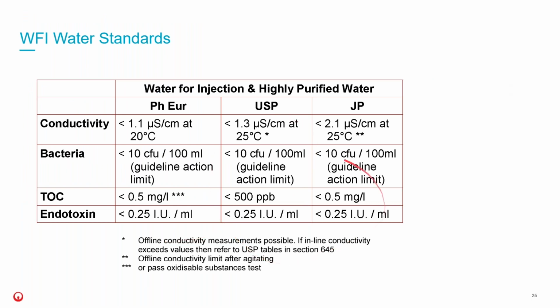So just to recap on the treated water qualities as set out by the various standards that we have to meet, if I just talk about the USP in this particular case: less than 1.3 microsiemens at 25 degrees, a tighter bacterial spec than purified water, less than 10 CFU per 100 mL. TOC remains the same at less than 500 parts per billion. And as I say, it's the fourth parameter, the endotoxins, which comes into play, and they're looking at less than 0.25 EU per mL.